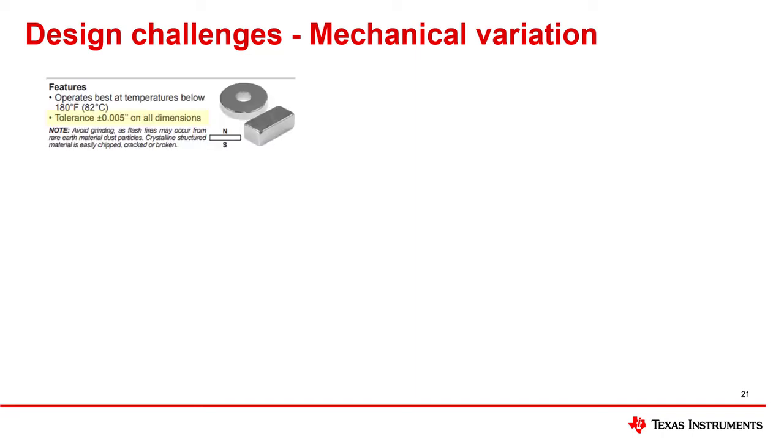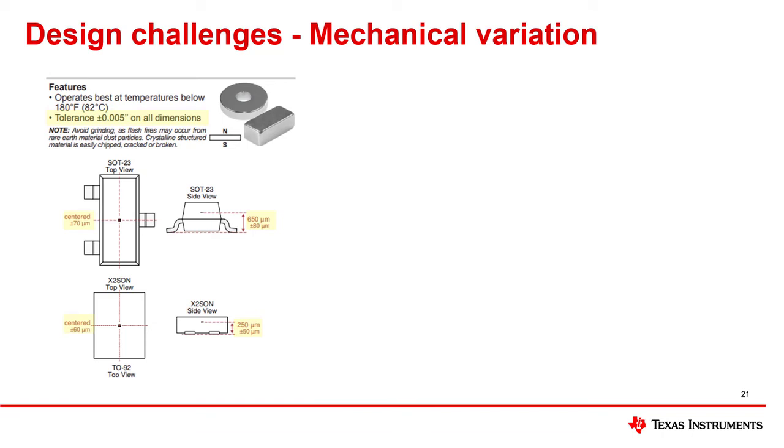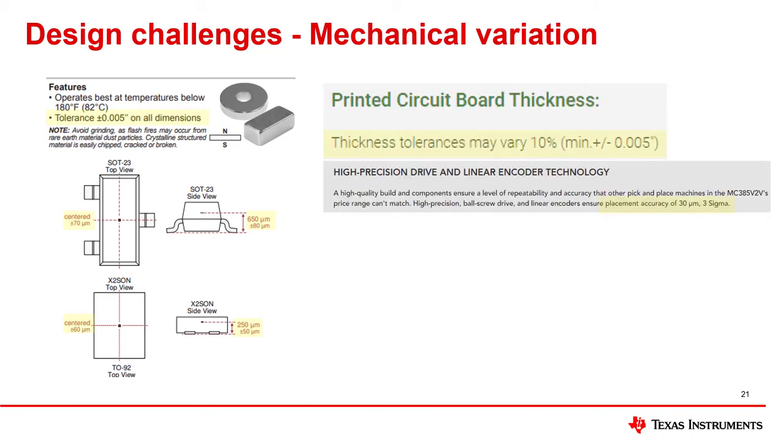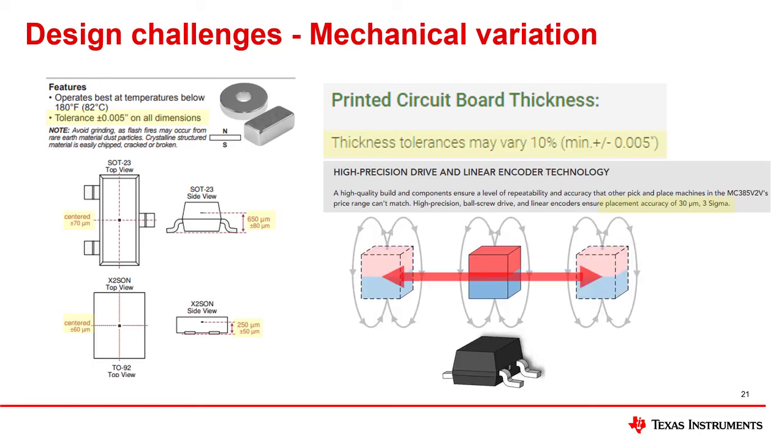As the design involves more than just the sensor, we can anticipate that there will also be variation due to tolerances in the manufacturing of the magnet, the Hall element placement within the device package, the Hall sensor PCB, the system fixture, and the physical placement of the magnet.